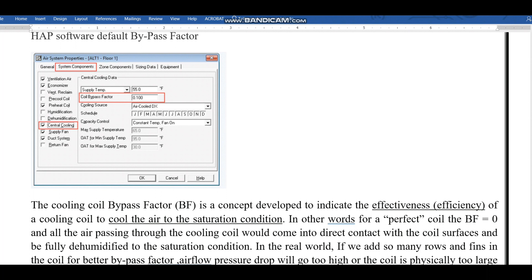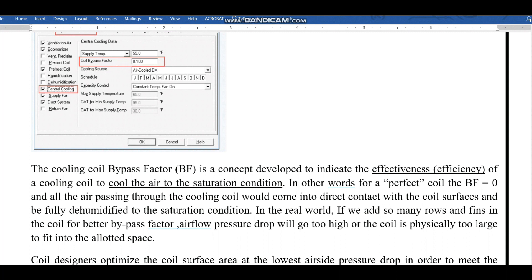The cooling coil bypass factor is a concept developed to indicate the efficiency or effectiveness of your cooling coil to cool the air to saturation condition. In other words, for a perfect coil, bypass factor would be zero, but it's not practically possible because all the air passing through would come into direct contact with the coil surfaces and be fully dehumidified to saturation condition. This is not possible in the real world.